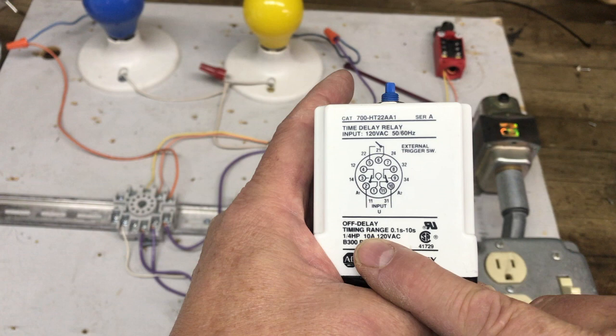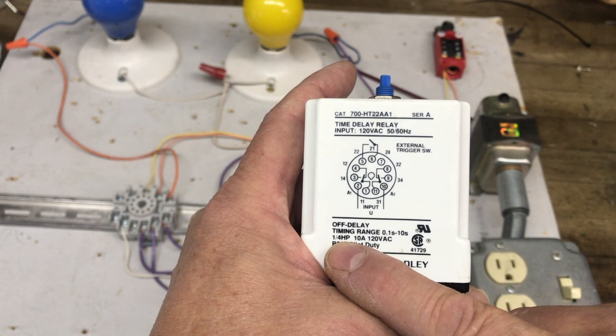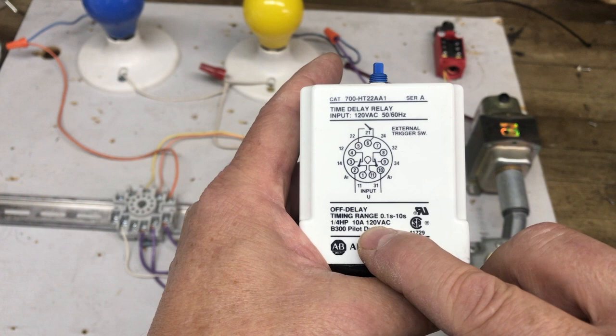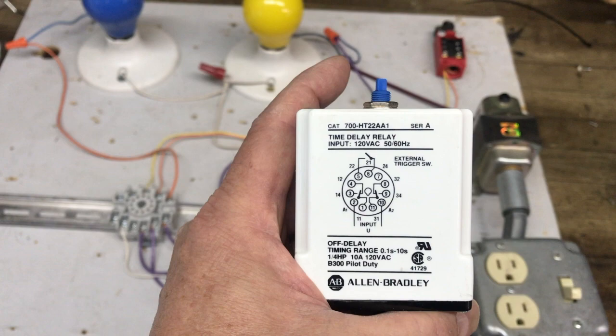The timing range is 0.1 seconds to 10 seconds, rated at a quarter horsepower, 10 amps, 120 volt AC. The quarter horsepower and 10 amps tell you how much the contacts can withstand, and 120 volts is the operating voltage for the coil. It also says input is 120 volts — that's the coil voltage — 50 to 60 Hz time delay relay.